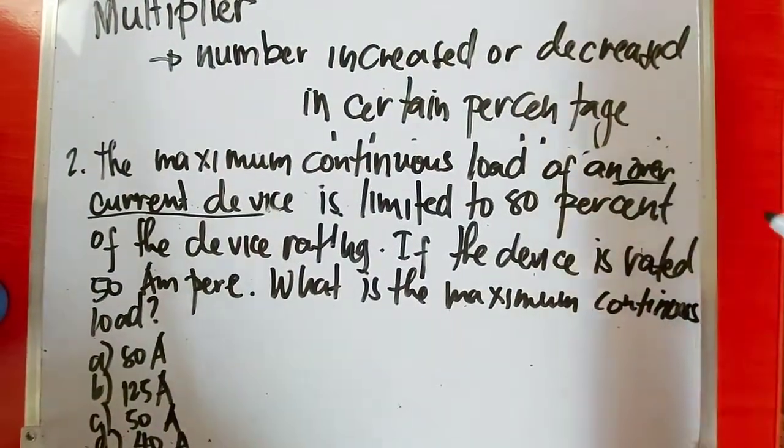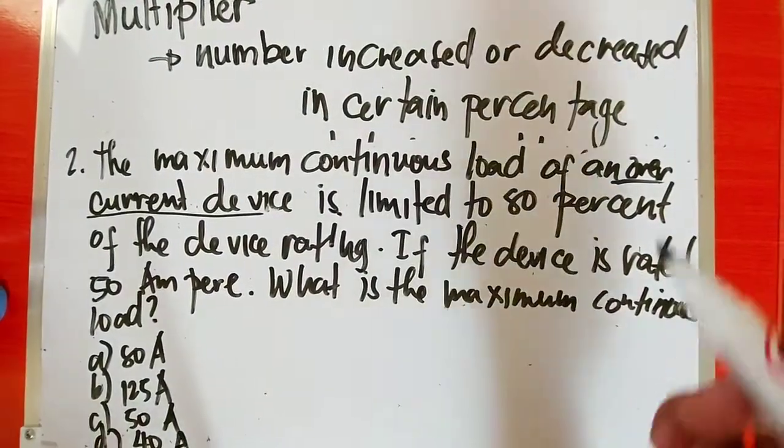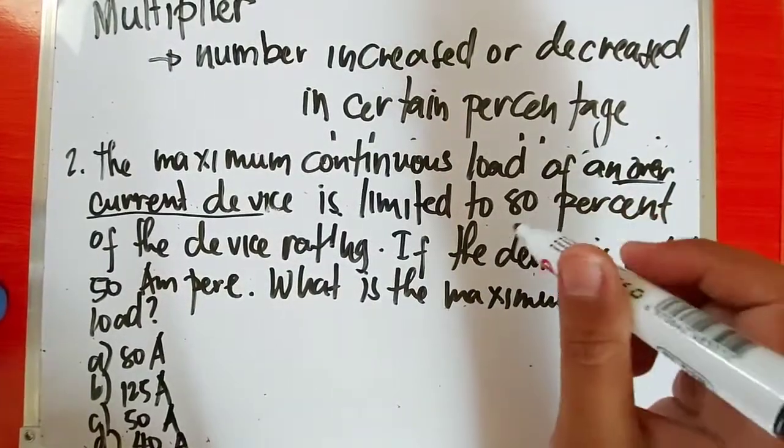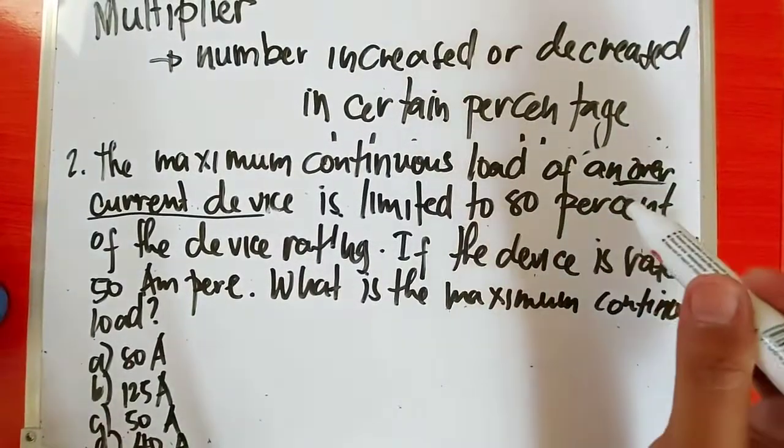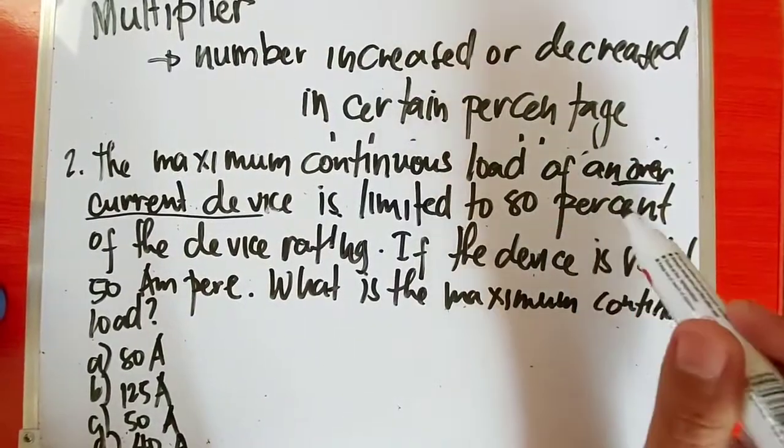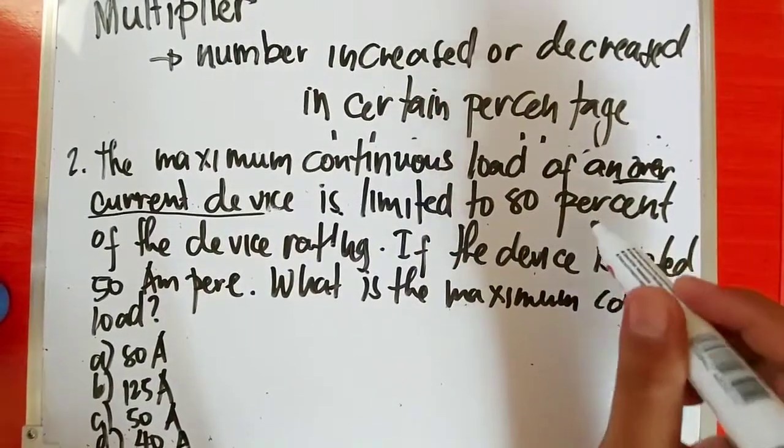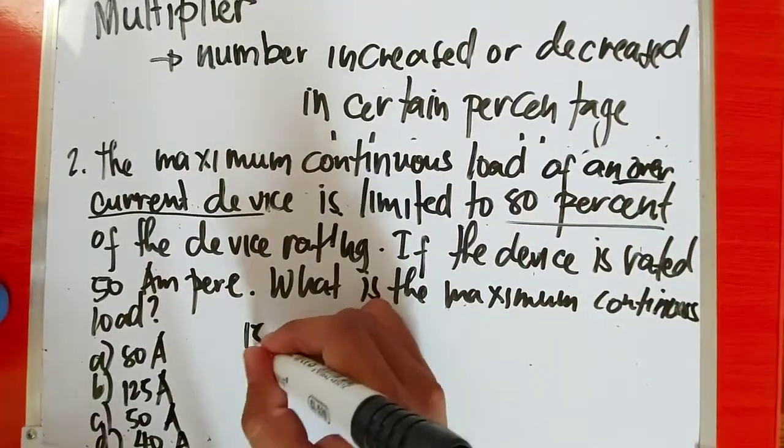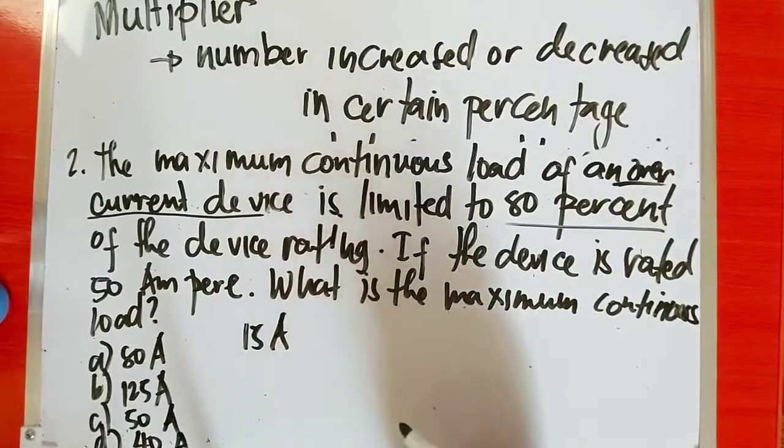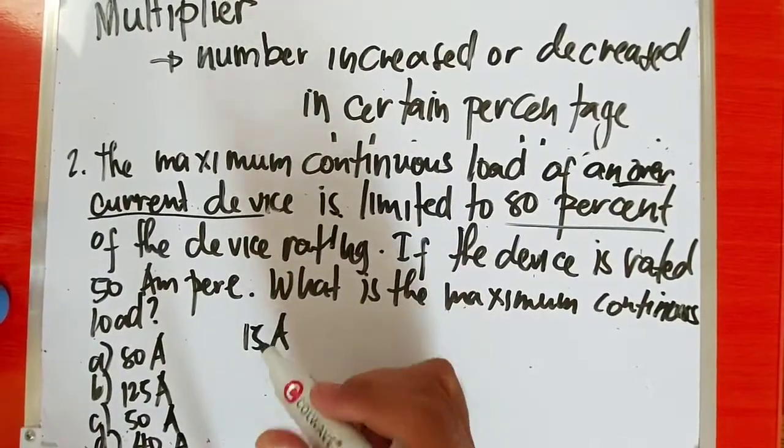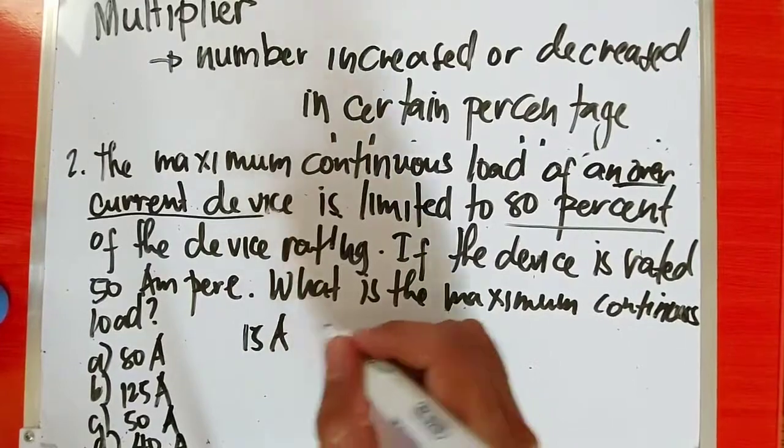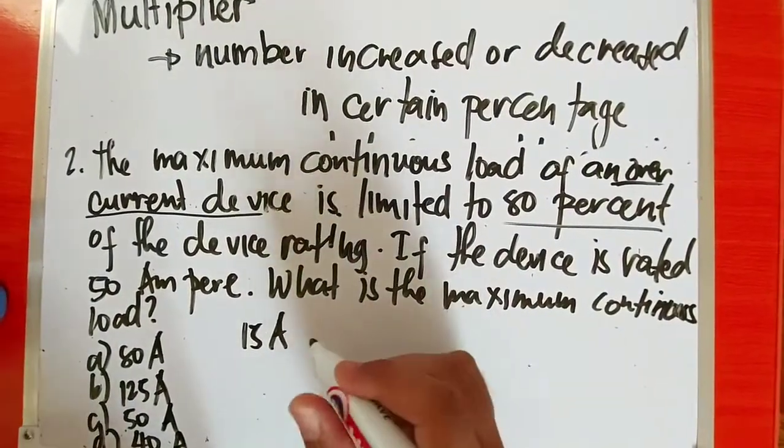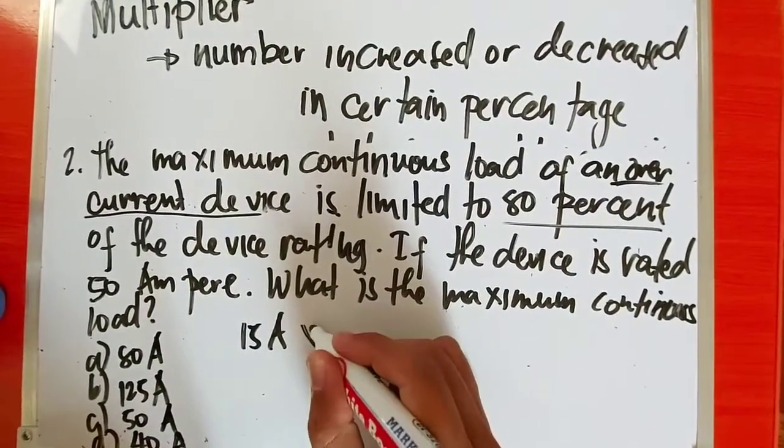The maximum continuous load of an overcurrent device is limited to 80%. So overcurrent device - what is that again? This is the fuse or circuit breaker. It's limited to only 80 percent, so it's derated. It's always like that. The overcurrent protective device is derated because you can't use it at 100% full capacity. It needs to be only 80 percent. For example, if I have a 15 ampere breaker, you can't use all 15 amperes. If you connect lights, you can't maximize the 15 amperes. You need to derate it by 80 percent.